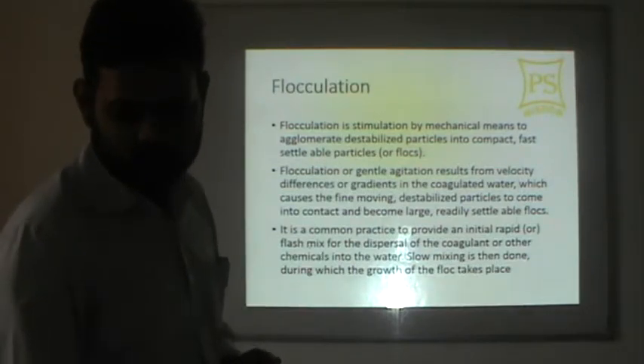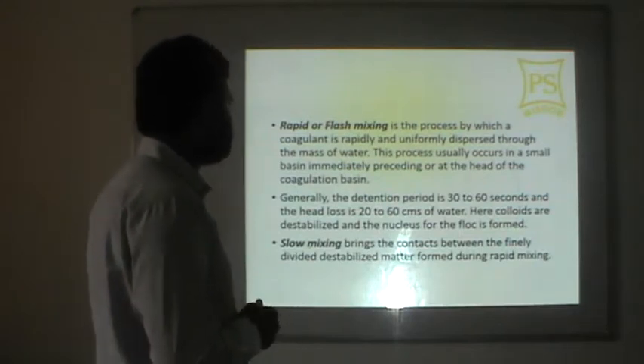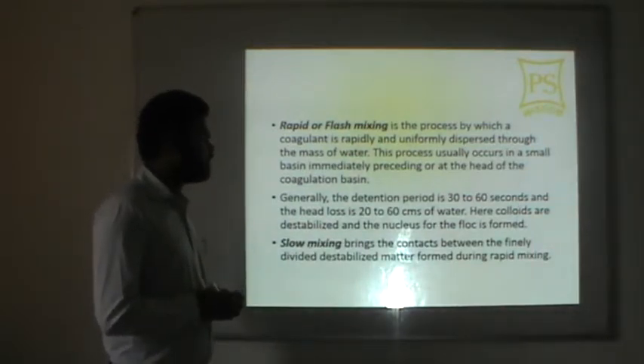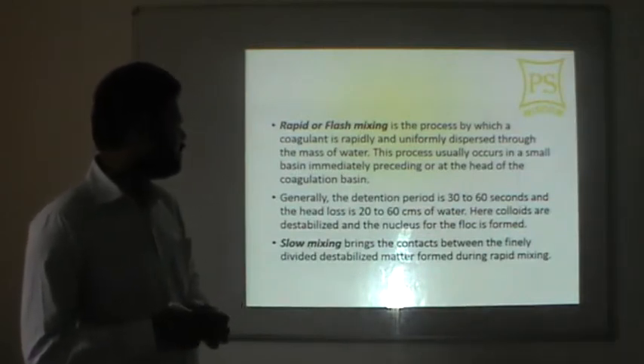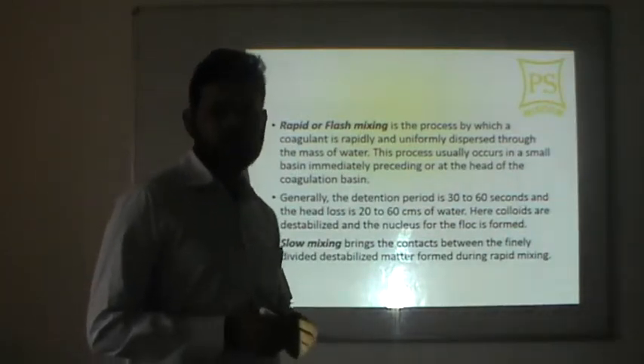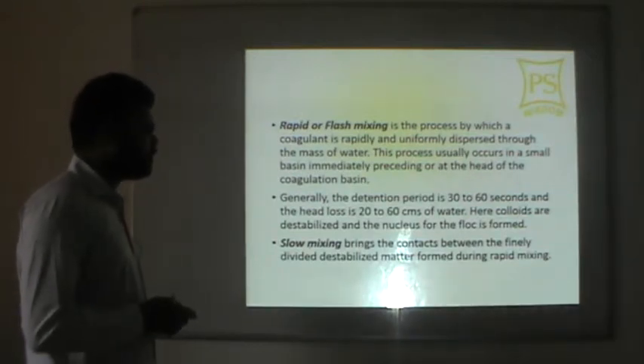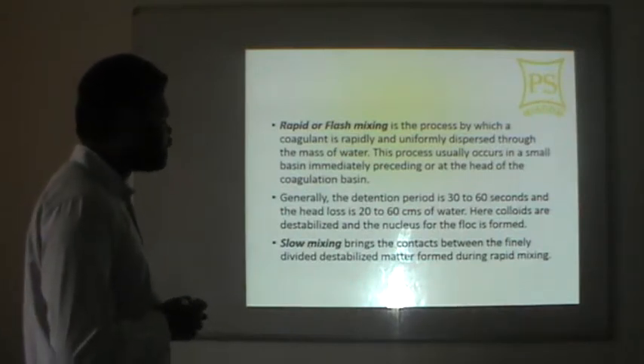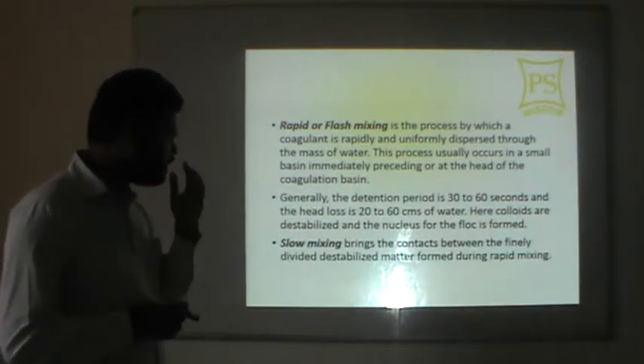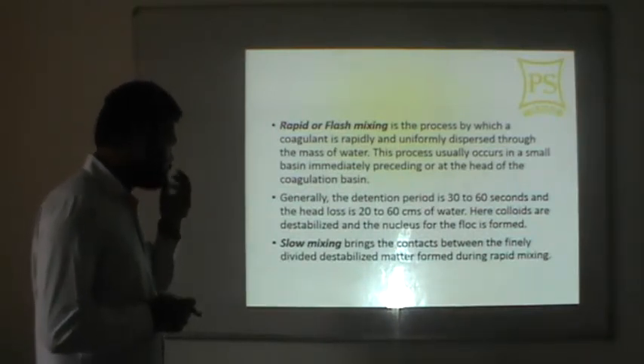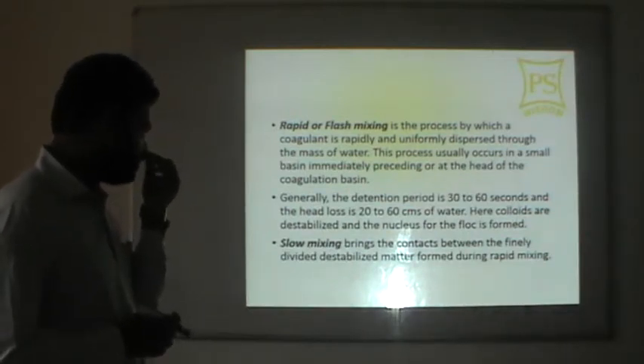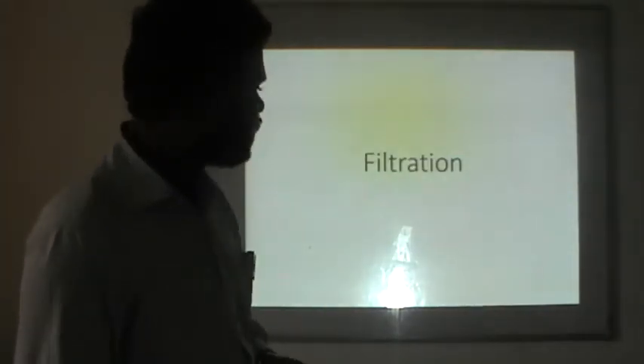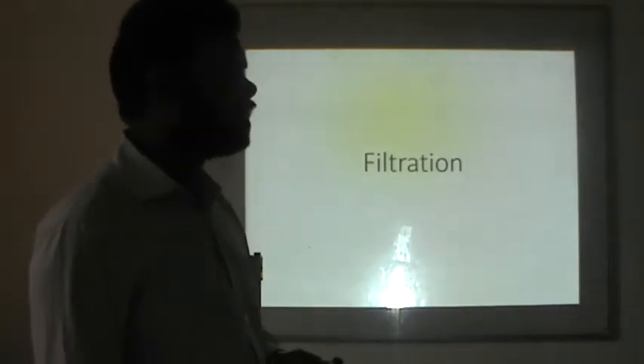Rapid or flash mixing is the process by which the coagulant is rapidly and uniformly dispersed into the mass of water. This process usually occurs in a small basin immediately preceding or at the head of the coagulation basin. Generally, the detention period is 30 to 60 seconds and the head loss is 20 to 60 cm of water. Colloids are destabilized and the nucleus for the floc is formed. Slow mixing then brings contact between the finely divided destabilized matter formed during rapid mixing.